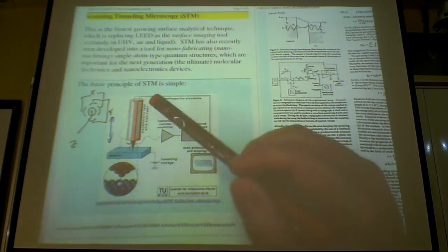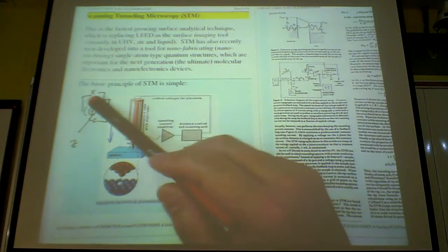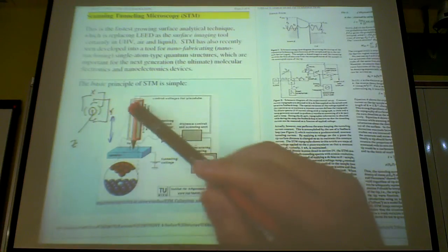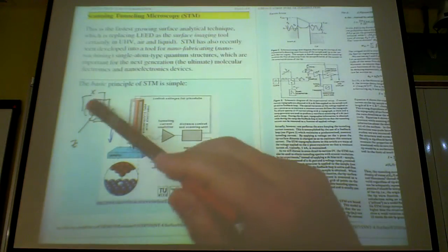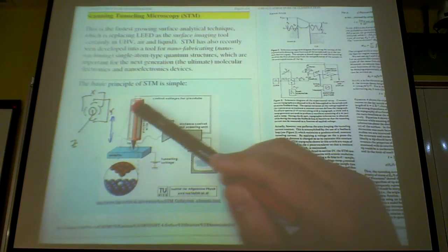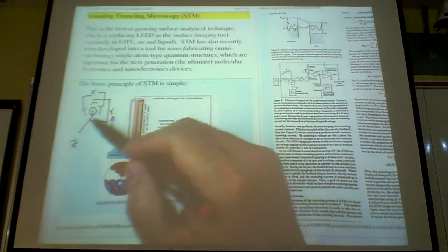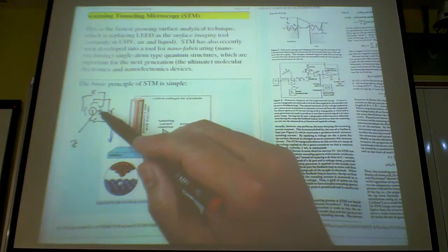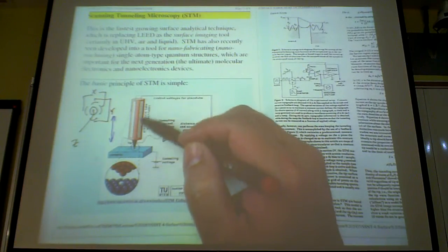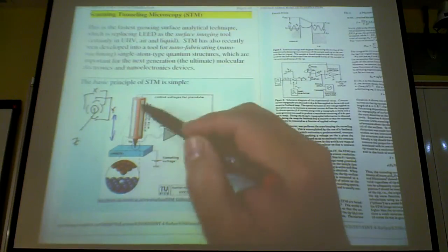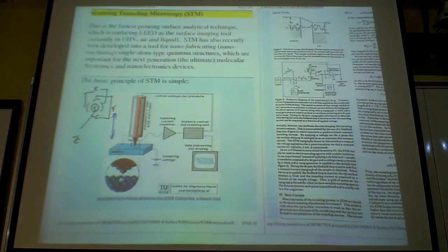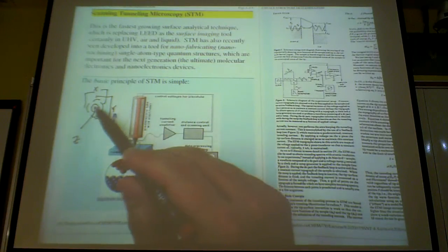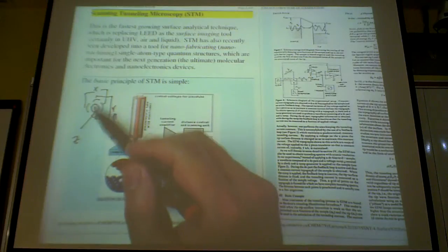And so what they have is essentially two sets of piezoelectrics, an X set and a Y set, right, like this is shown on these. This is a looking-down version of this column. So you have X and Y, and you can apply the voltage. You can mount your tip on here, so you can pull and push, if you like, on this column, and then you can scan in the XY direction depending on the voltage you apply in the X piezo or the Y piezo.